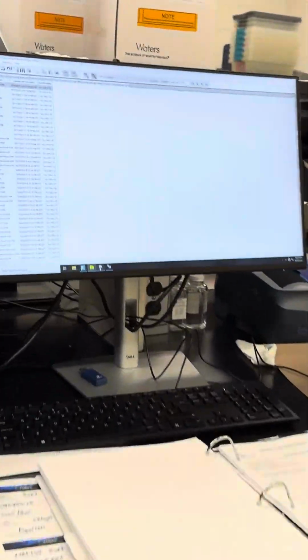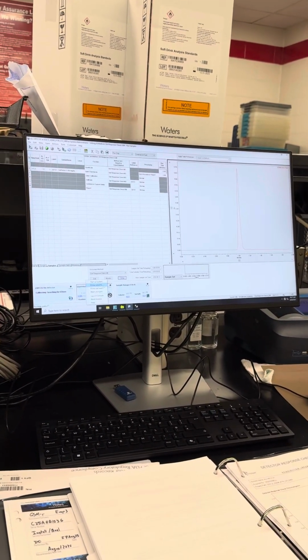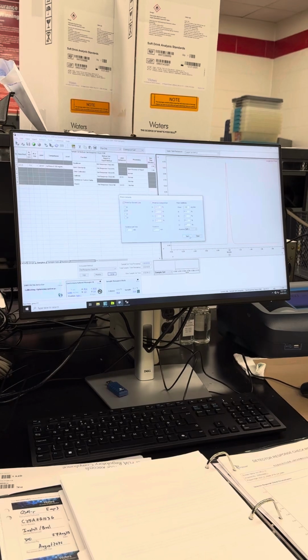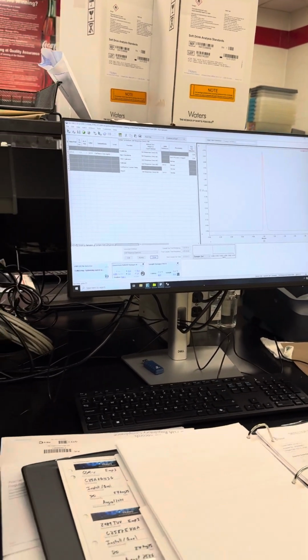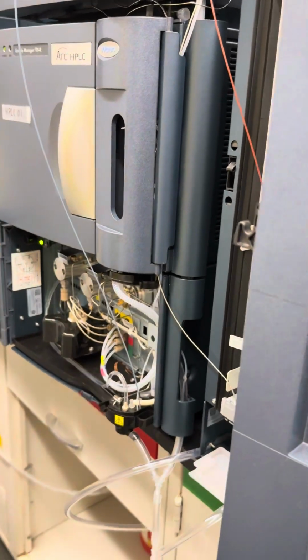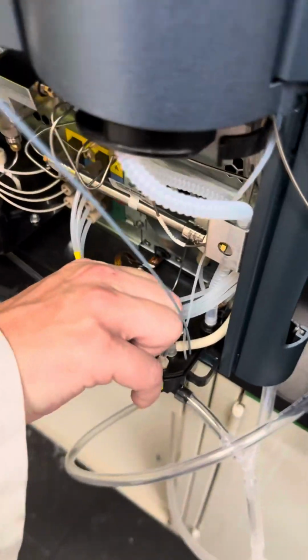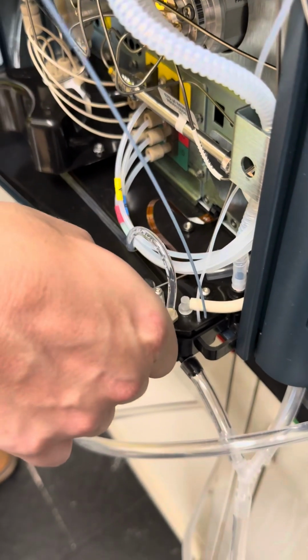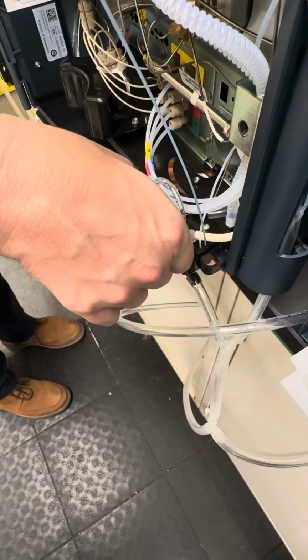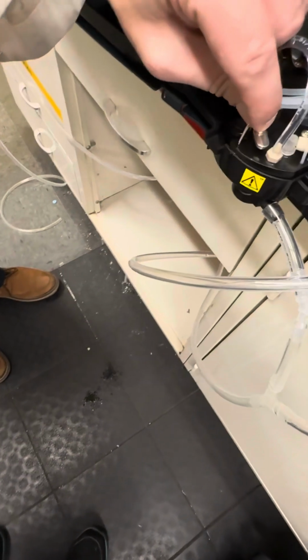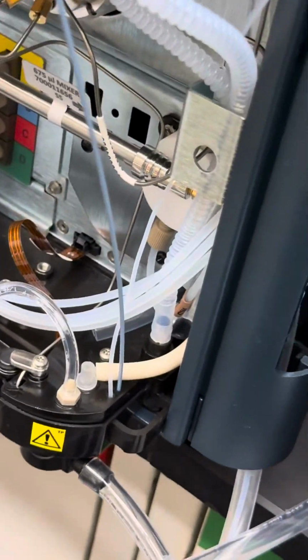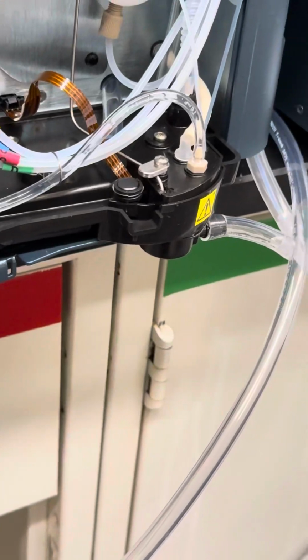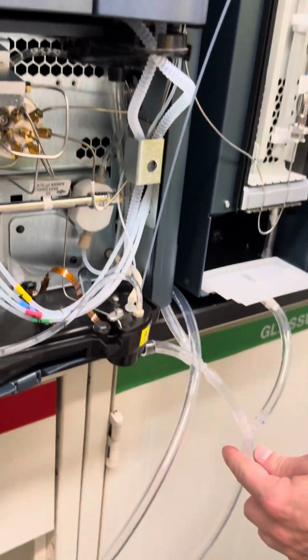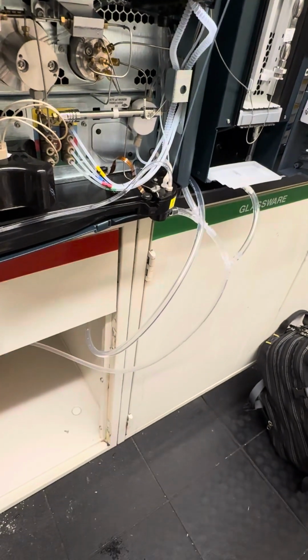Let me show you if we prime it. So once again, we go here. I want to prime this. Prime solvents, for a minute, start. So it's gonna start priming. As I said, if we pull this out, we can see that it'll start flowing. So you'll see it starts flowing. You want that to be nice and smooth, no pulses or anything like that. And now it's priming, it's going to the waste line through here and dropping down to your waste. So it's there.